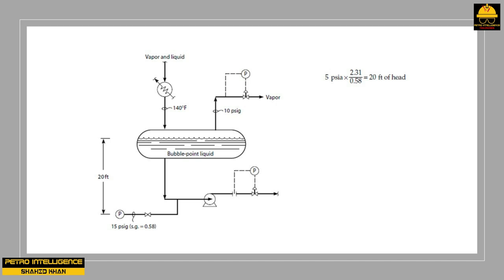Suppose we decrease the temperature of the drum from 140 to 110 degrees Fahrenheit, also cooling the liquid flowing into the suction by 30 degrees Fahrenheit. This does not provide more NPSH either. As the temperature decreases, additional lighter components dissolve in the liquid, altering its composition. The liquid will now boil not at 140°F but at 110°F, because the liquid in the drum, in equilibrium with the vapor, is at its bubble point temperature — now a cooler 110°F.